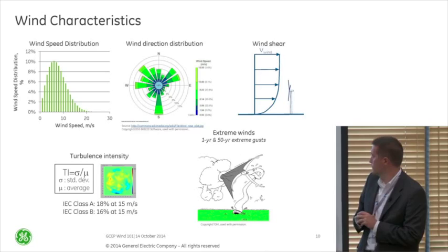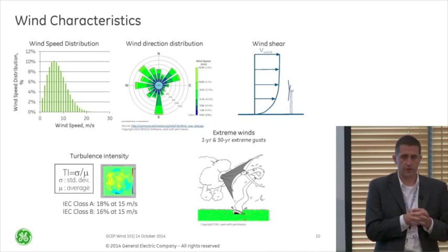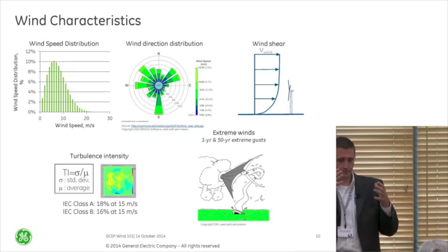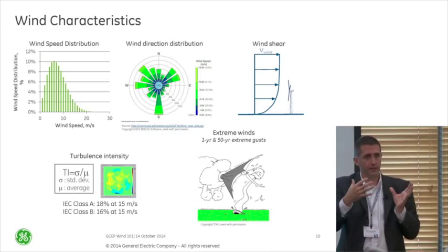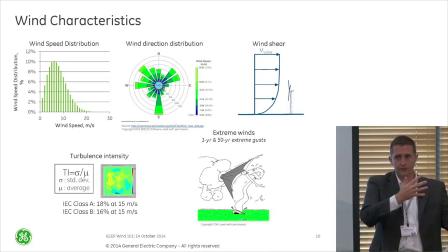Directional changes are especially important on a time basis — if you're in some sort of weird mountain range with a valley, you might get wind shooting from different directions. That can become a big problem because now I don't have enough time to yaw back and forth to really capture that wind. So that can be a red flag in terms of siting a wind turbine — even though you might have a great wind resource, if the direction is shifting on a really short time scale, it becomes tough for some of these wind turbines to handle.